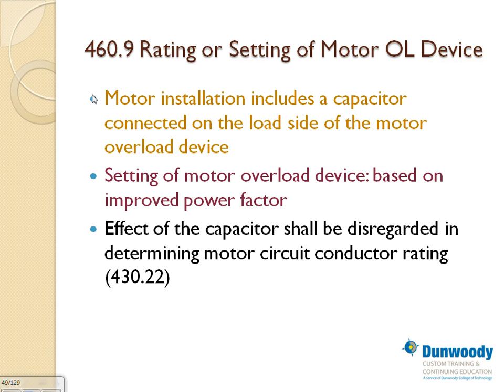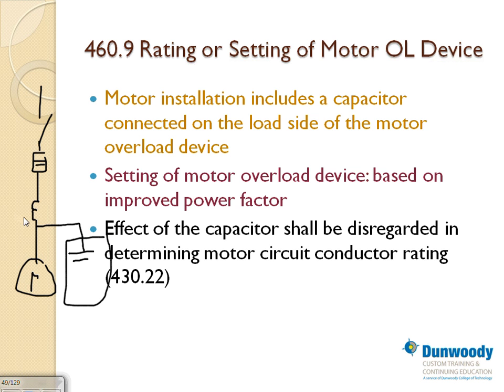In terms of conductors, don't do anything with the conductors, just the overload. What we're trying to say here is, here's a fuse, here's a disconnect, and here's my overload, and here's my motor. Right on the load side of the motor, I added a capacitor bank. I forgot to show the controller here. They will have a controller. Every time you push the button, you energize the motor, and at the same time you energize the capacitor bank with it. In this case, the overload will be seeing the improved power factor.